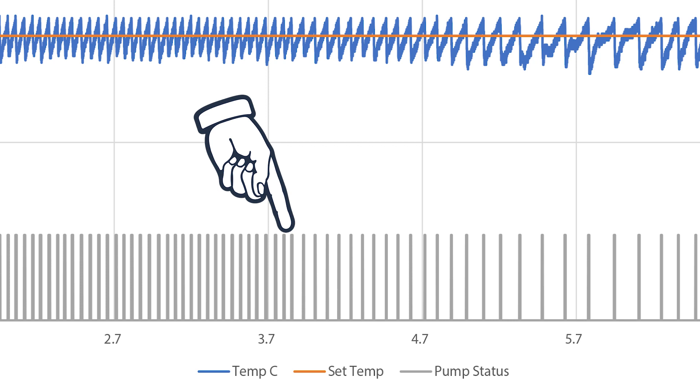And you can see right here is where I put the jacket on. So you can see the intervals at which the pump turned on. Those intervals grew in size, meaning we didn't need as much cooling when we had the insulation and jacket all zipped up tight.